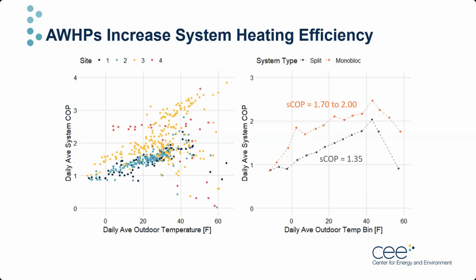Site 3 had the best average daily system performance as the only site that did not have major controls modification related to auxiliary heat used during the study. Comparatively, Site 4's average COP between 10 Fahrenheit and 50 Fahrenheit was substantially reduced by regular propane usage, which has been filtered out for this diagram. This is also the reason why there are so few red dots on the left side.